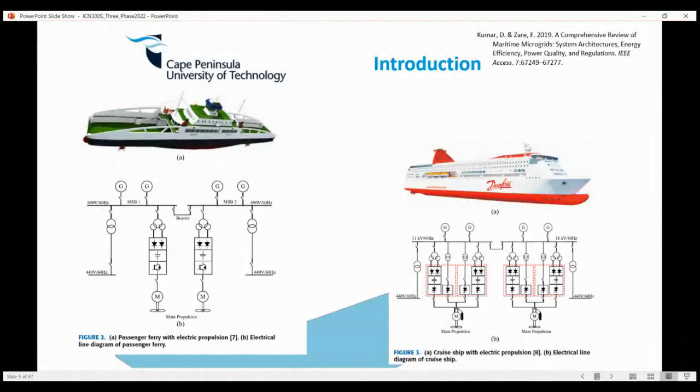So if you look at the thing on the left, do you have to know this? No, but like I said to you, it's just to provide some preamble in terms of what we're going to be doing. So you've got a generator, a three-phase synchronous generator, producing 690 volts at 60 hertz. Then you guys can see my mouse. Then we've got a single-phase transformer over there, stepping it down to 440 at 60 hertz.